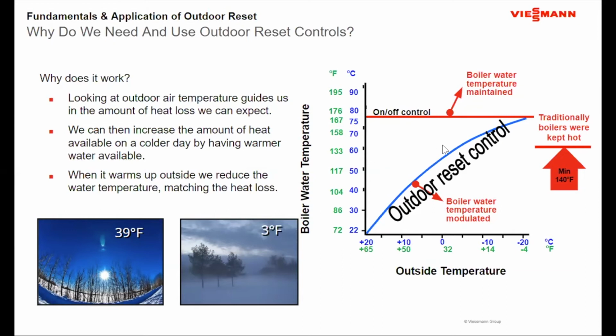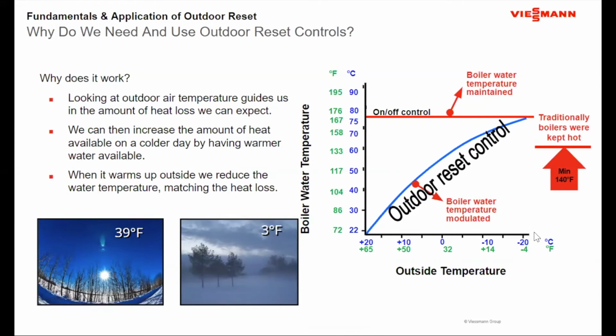The key really is I have to make sure I choose the right heating curve to maintain that temperature. And usually from an aspect of design, it's all about ensuring that one end of it is anchored to design conditions. Mine is 0 degrees Fahrenheit, 180-degree water. So I know that becomes one of my tie-in points.